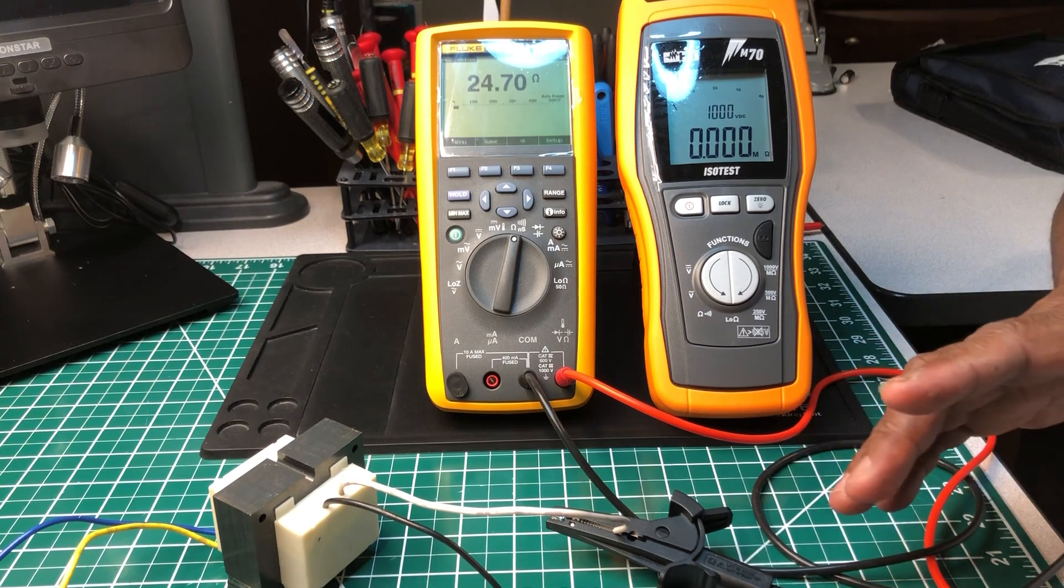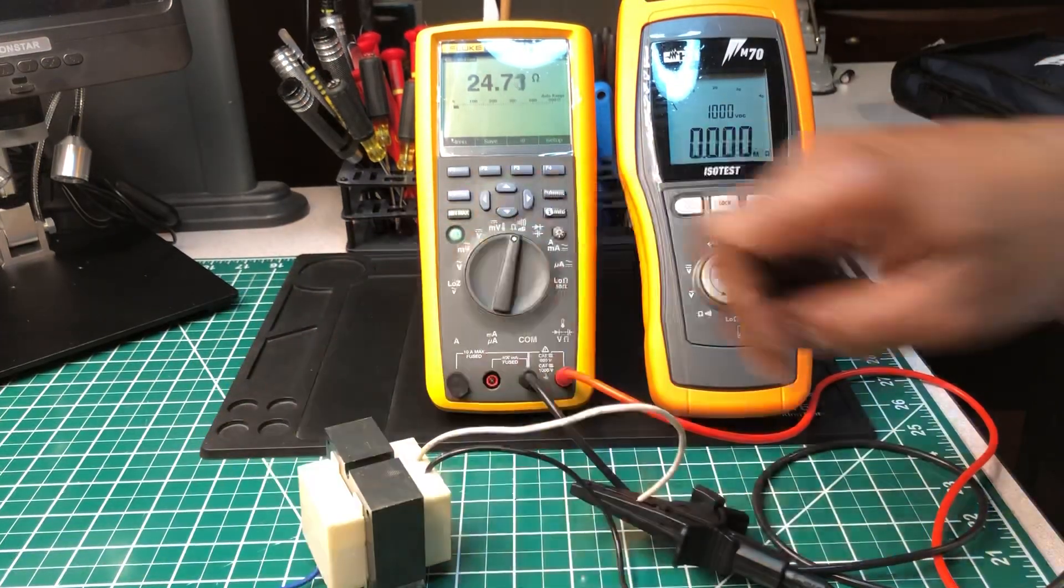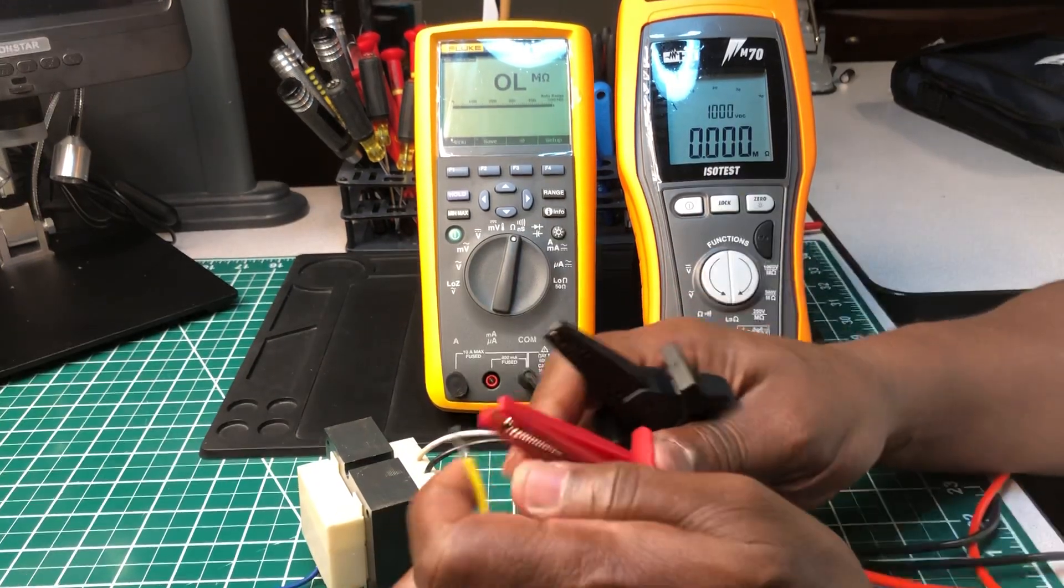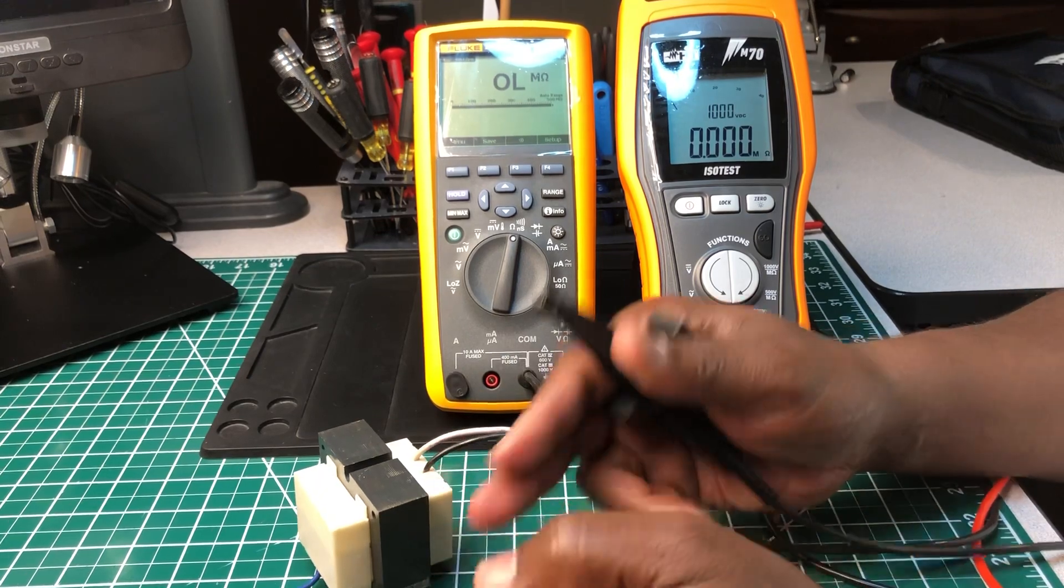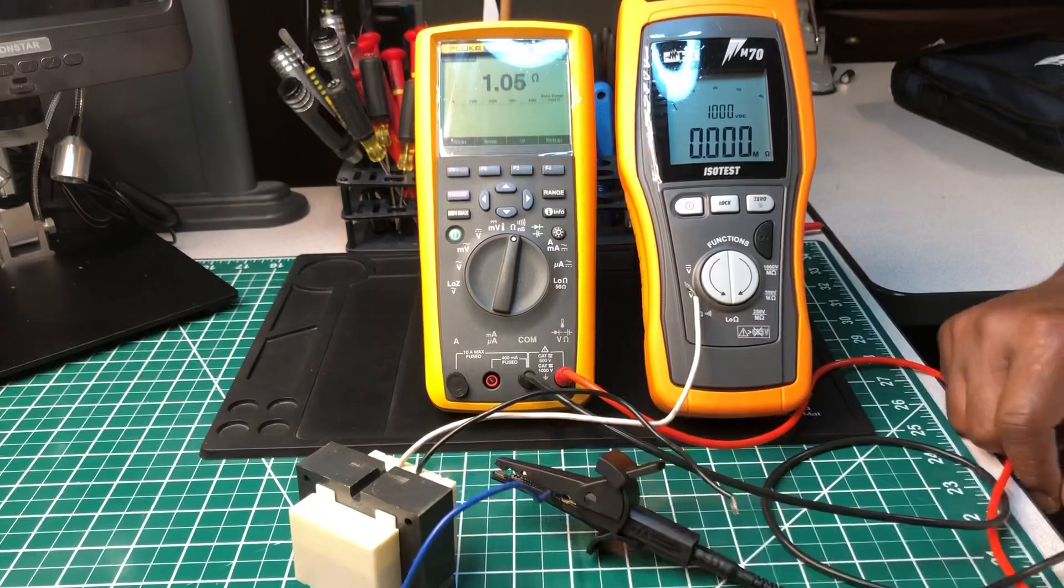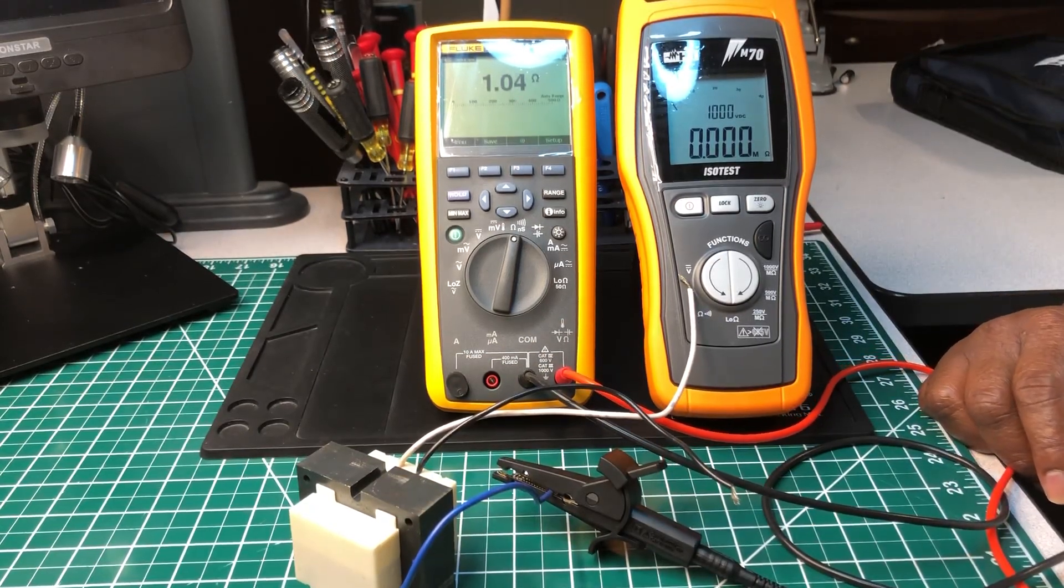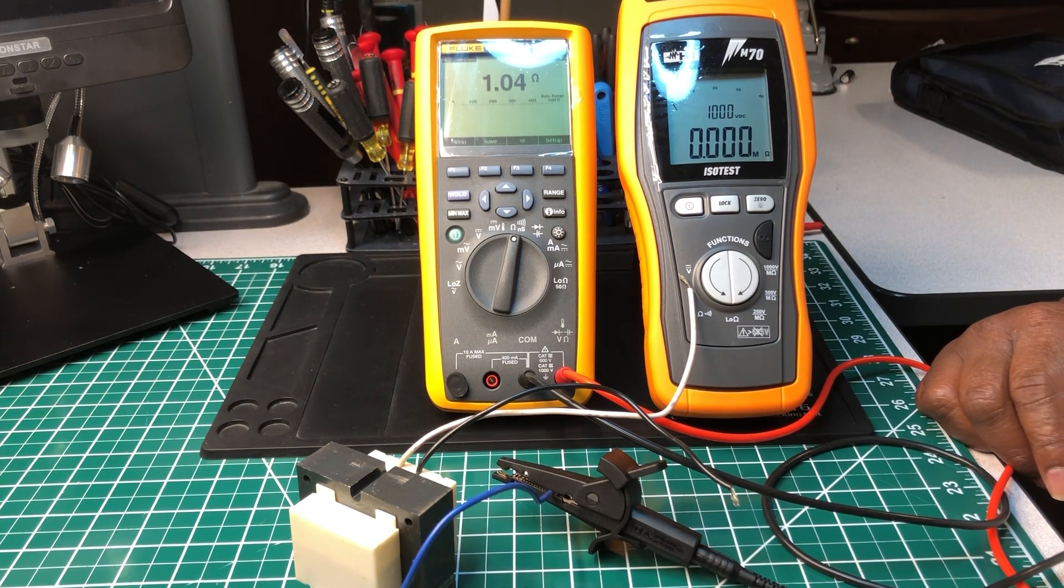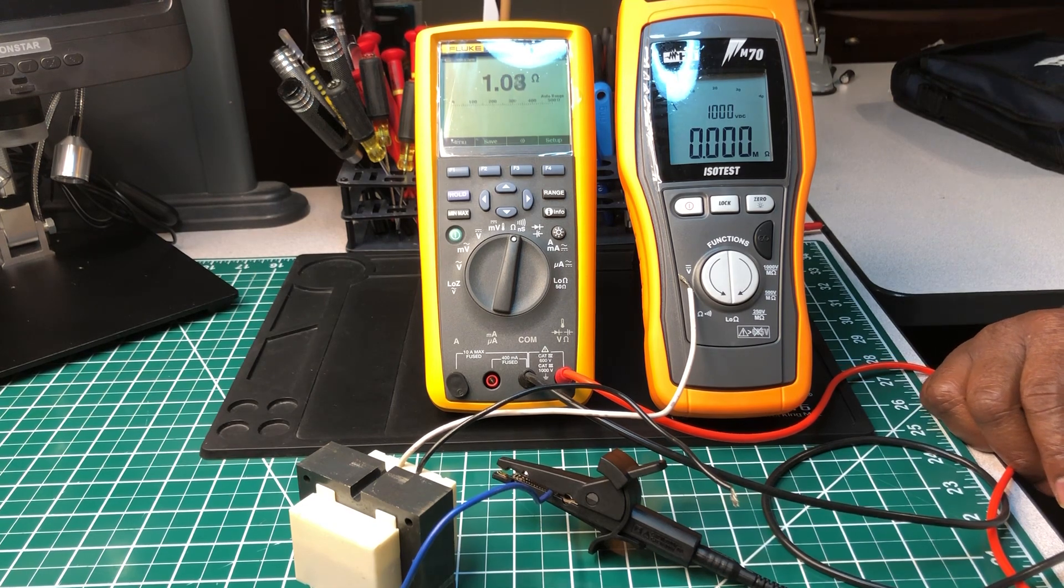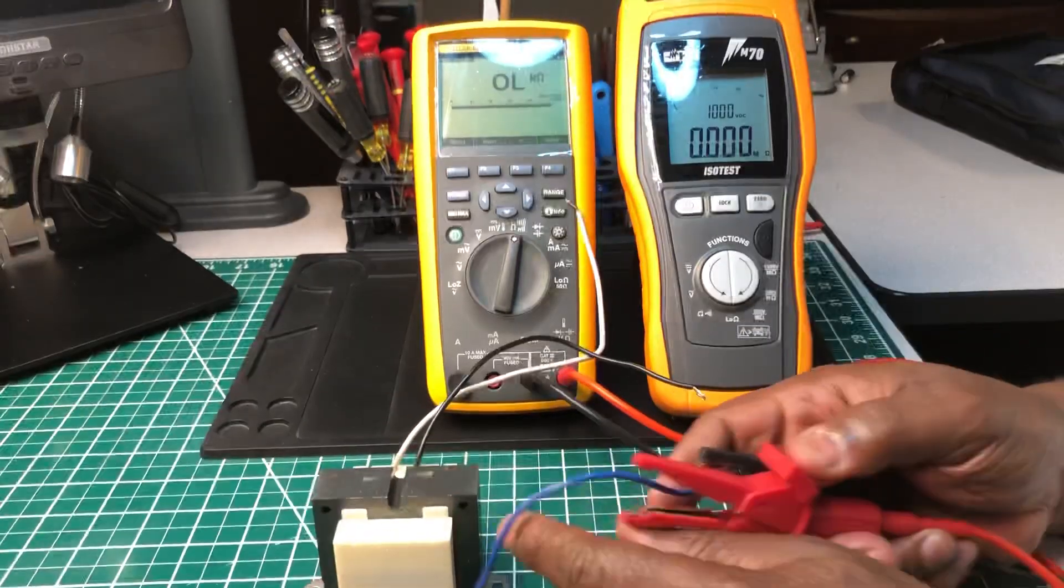Let's just say you're questioning it, you want to be sure. Let's go to the secondary side also. Let's do the same thing to the secondary side and we'll see. Now remember, this is a step-down transformer. You're getting 1.04 ohms on that side, so the transformer is good on the secondary side and the primary side.